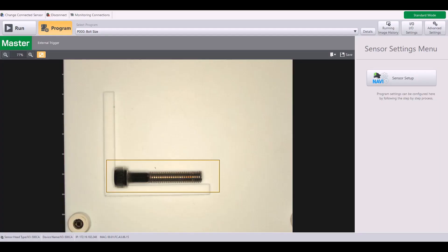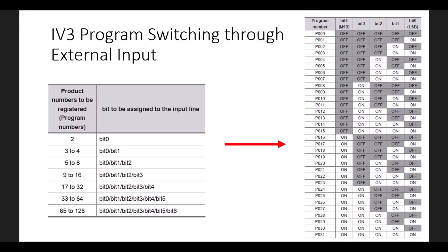In this video, I'm going to walk you through how to set up program switching by using the external inputs on the IV3. The first thing we need to consider is how many programs we need to be switching between. These charts can be found in the IV3 users manual.